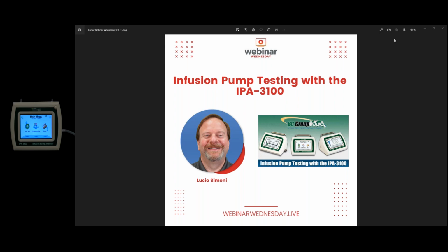Okay, so how many pumps can the analyzer check at one time? Can it handle multiple channel IV pumps such as the Plum 360 or Alaris? Oh, that's a good question. So this particular unit, the 3100, can only measure one infusion pump at a time. And while that pump is connected, you can do your occlusion testing and your flow testing. You can do all the tests that you need to do, or multiple tests on that one pump. But for measuring multiple channel pumps, you would need to use an IPA 3400, which gives you up to 4 channels.